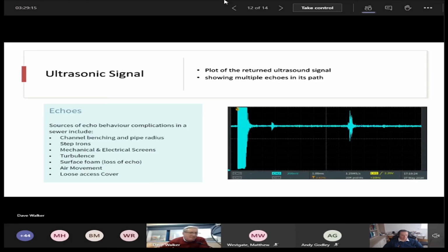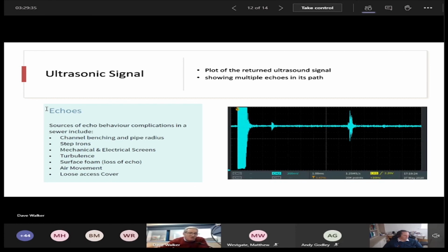Okay, so things we have to look out for, which are pretty standard and straightforward in a chamber: channel benching and pipe radius, which may refract the energy coming back from the sensor. Step irons in the way, mechanical and electrical screens, as I mentioned earlier about electrical noise, turbulence, surface foam, loss of echo, air movement if it's a large open channel. Loose access covers. Yeah, we're dealing with noise here. So you've got a loose access cover and it creates a big bang. Then what's that going to do to our sensors in the sewer network?